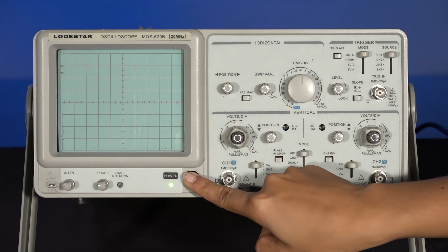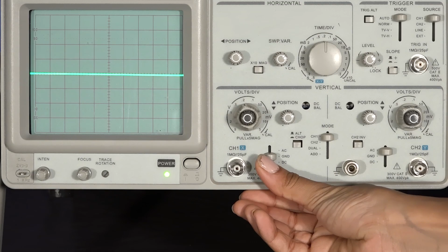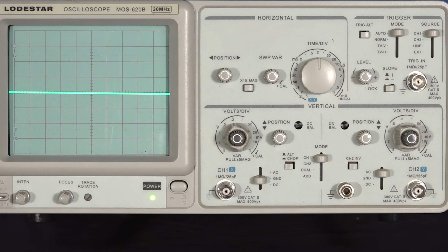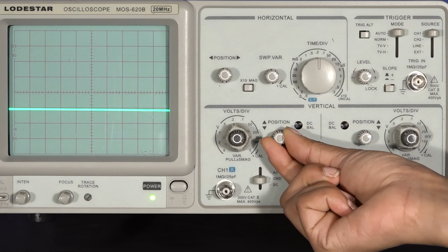We can adjust the brightness and focus of this trace. To make sure that the horizontal line represents the zero voltage level, we place the input selector switch to the ground position and observe the line. If the line is shifted from the horizontal axis, we can use the vertical position controller to bring it back.